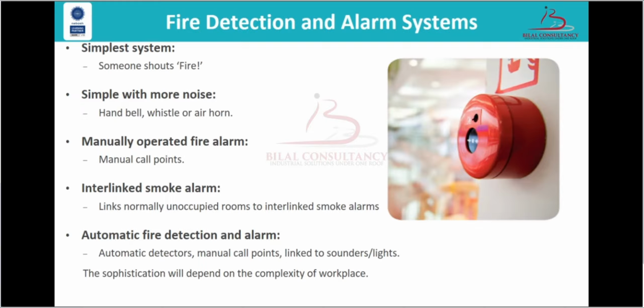The next step up is a fire alarm system that can be manually activated from call points. These call points are usually buttons behind a clear plastic disc. When hit, they break and activate the system. The system will have a central control box and sounders at positions throughout the workplace that give the alarm. Interlinked smoke alarms: if there are rooms such as a plant room or store that are not normally occupied, so a fire might start there and no one would notice, then a simple automatic detection and alarm system might be fitted. Made up of interlinked smoke alarms, this consists of individual ceiling mounted units that detect smoke from the fire and give the alarm sound. These are linked together so that when one sounder activates, all of the sounders emit the alarm.